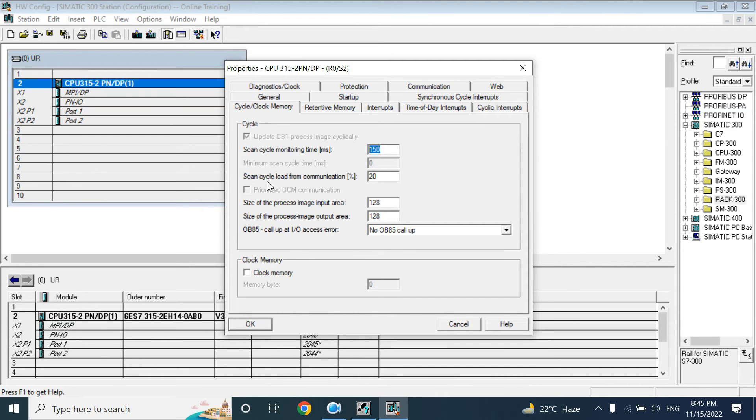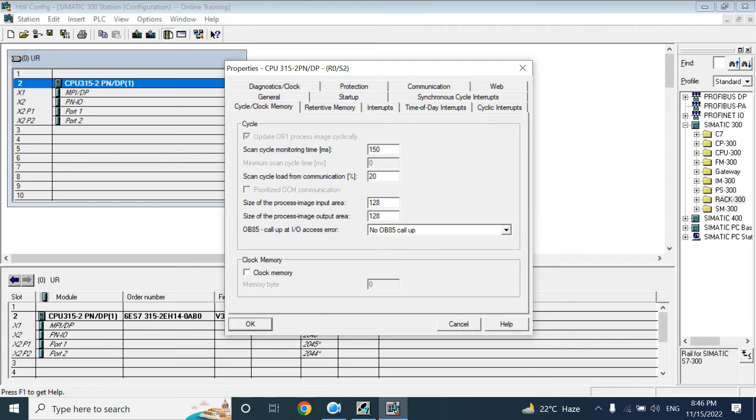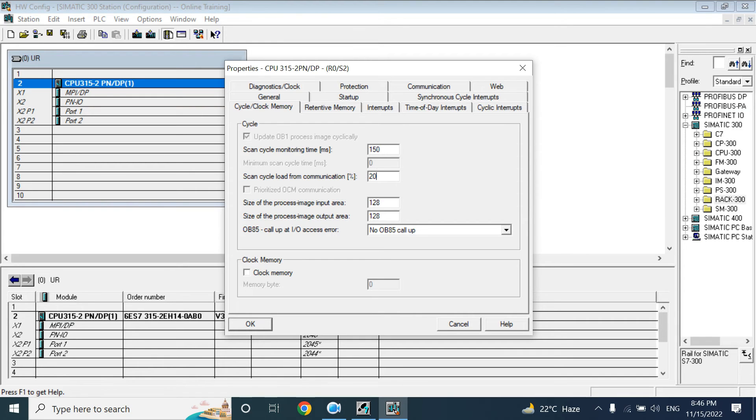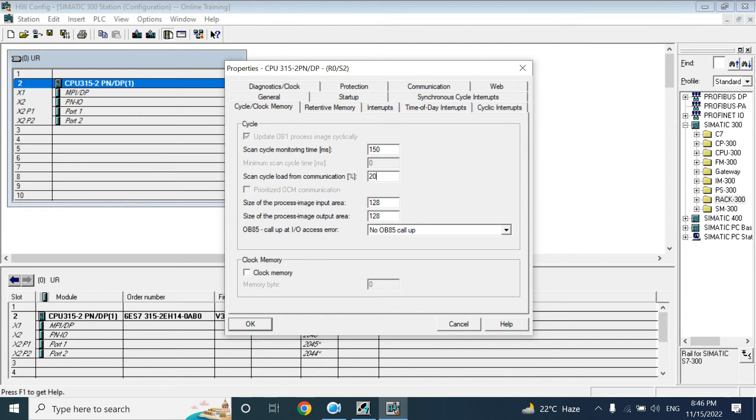Here, scan cycle load from communication will add extra 20%. That means 150 milliseconds, 20% of 150 milliseconds is 30 milliseconds. So total 180 milliseconds is considered as maximum cycle time. And that 20%, 20% of that 150 milliseconds, is used for the communication. That for your PC, that programming device, or your HMI or the drive communication, SCADA communication. Both will take by this 20% from 150 milliseconds.